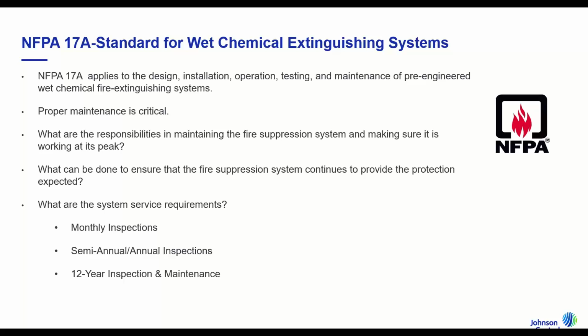What can be done to ensure that the system continues to provide the protection expected? Make sure that we do those semi-annual services, make sure that we're doing our monthly inspections, and also the 12-year inspection and maintenance. All of these things are important, vital, and key to maintaining a restaurant fire suppression system's integrity and ensuring that it will be there to work when called upon.